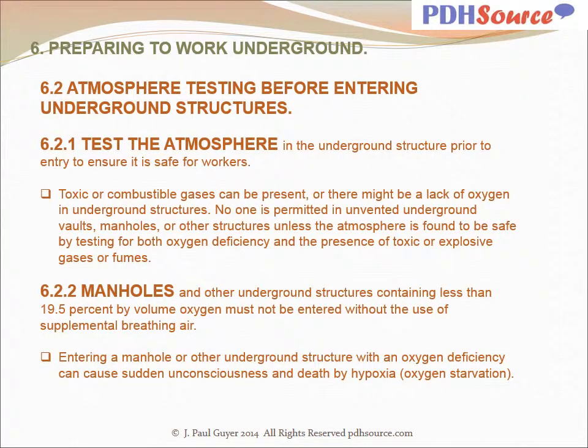Test the atmosphere in the underground structure prior to entry to ensure it is safe for workers. Toxic or combustible gases can be present, or there might be a lack of oxygen in underground structures. No one is permitted in unvented underground vaults, manholes, or other structures unless the atmosphere is found to be safe by testing for both oxygen deficiency and the presence of toxic or explosive gases or fumes. Manholes and other underground structures containing less than 19.5% by volume oxygen must not be entered without the use of supplemental breathing air. Entering a manhole or other underground structure with an oxygen deficiency can cause sudden unconsciousness and death by hypoxia, oxygen starvation.